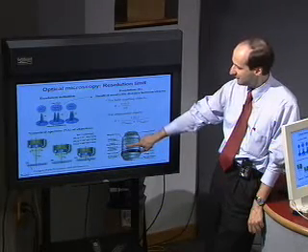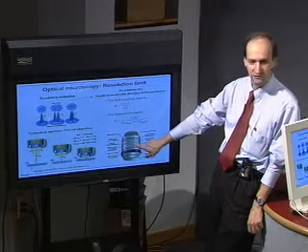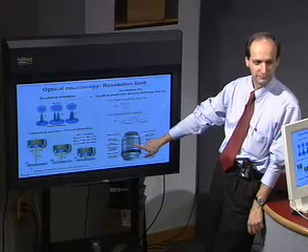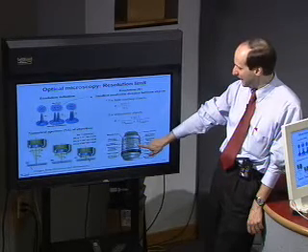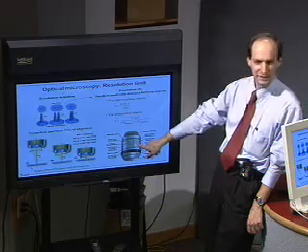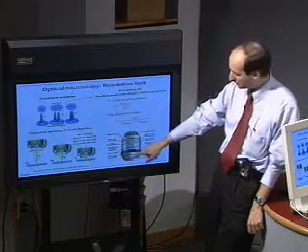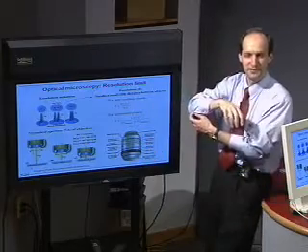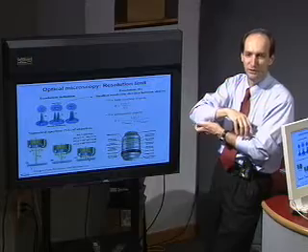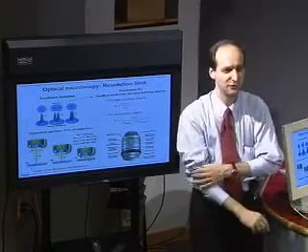So it's magnification 60 times at a numerical aperture of 1.40. This is a very high numerical aperture, and it is very high because, as you can see here, this objective needs oil. You have to put a droplet of oil between your objective and your sample. If you don't put a droplet of oil, then you can try to focus hard, and you're going to see some very unclear images.